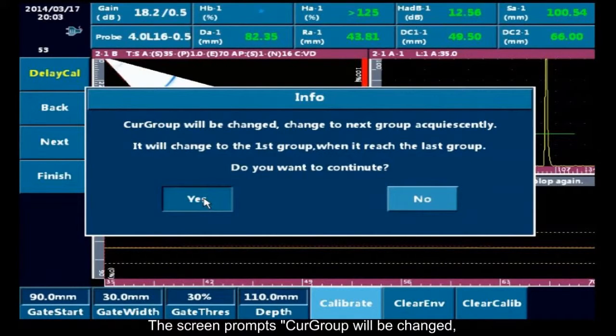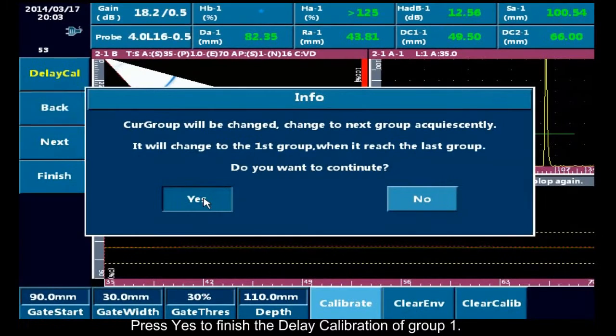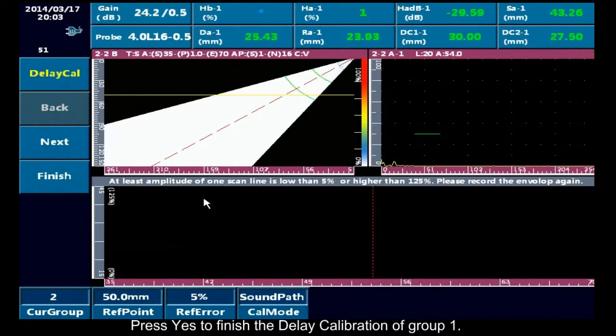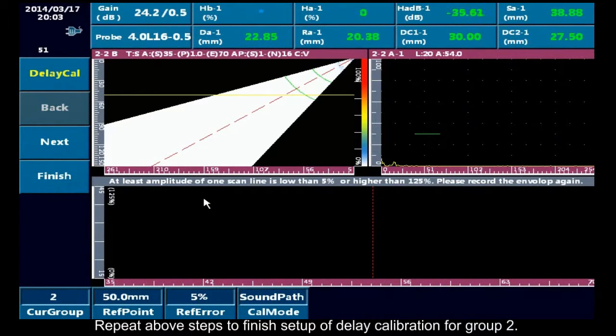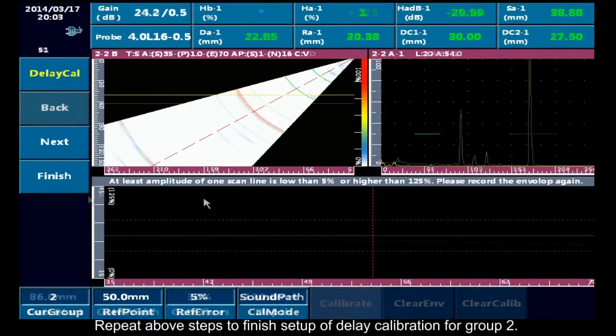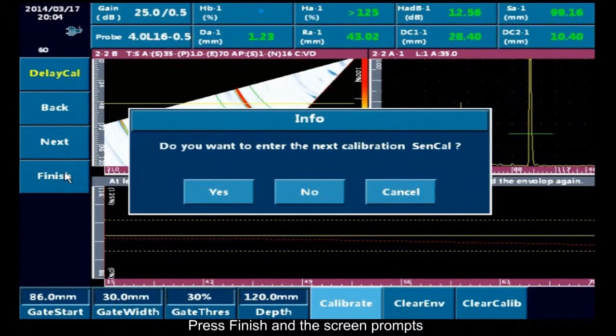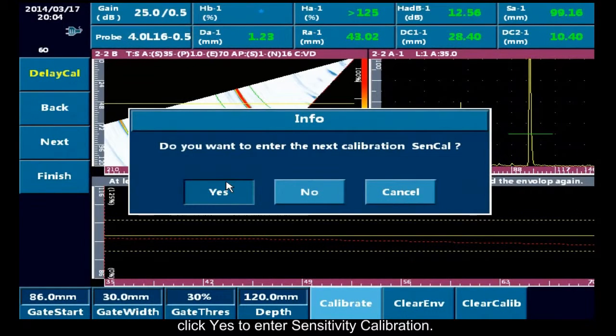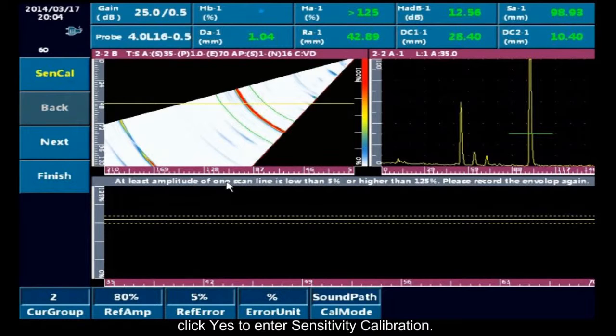The screen prompts CurGroup will be changed. Change to next group acquiescently. It will change to the first group. When you reach the last group, do you want to continue? Press yes to finish the delay calibration of group 1. Repeat above steps to finish setup of delay calibration for group 2. Press finish and the screen prompts, do you want to enter the next calibration, sensitivity calibration? Click yes to enter sensitivity calibration.